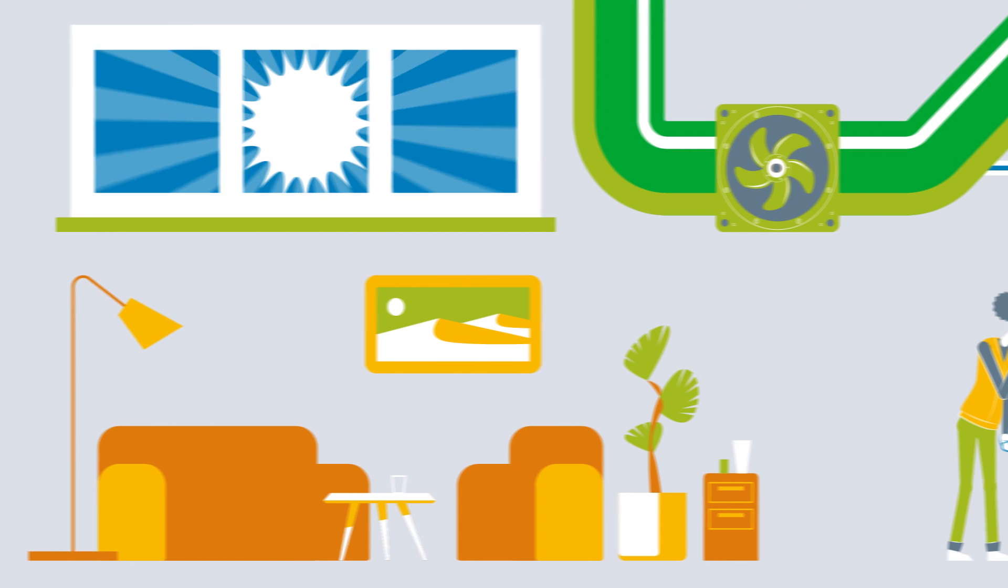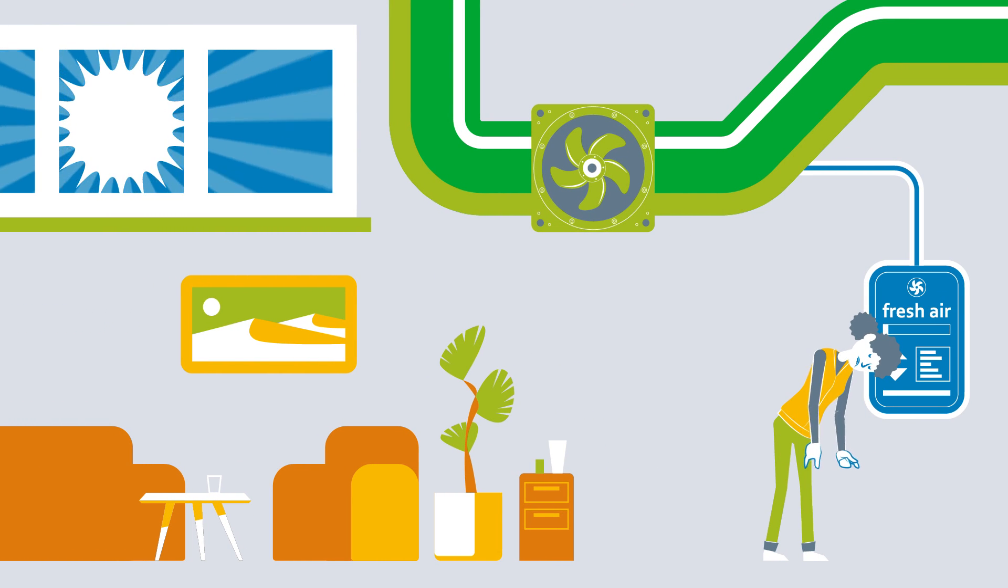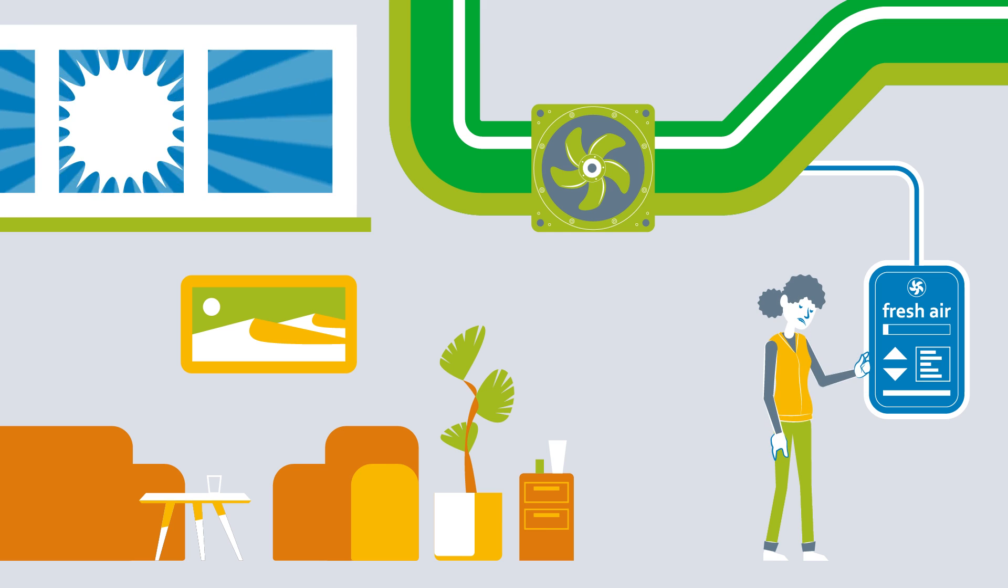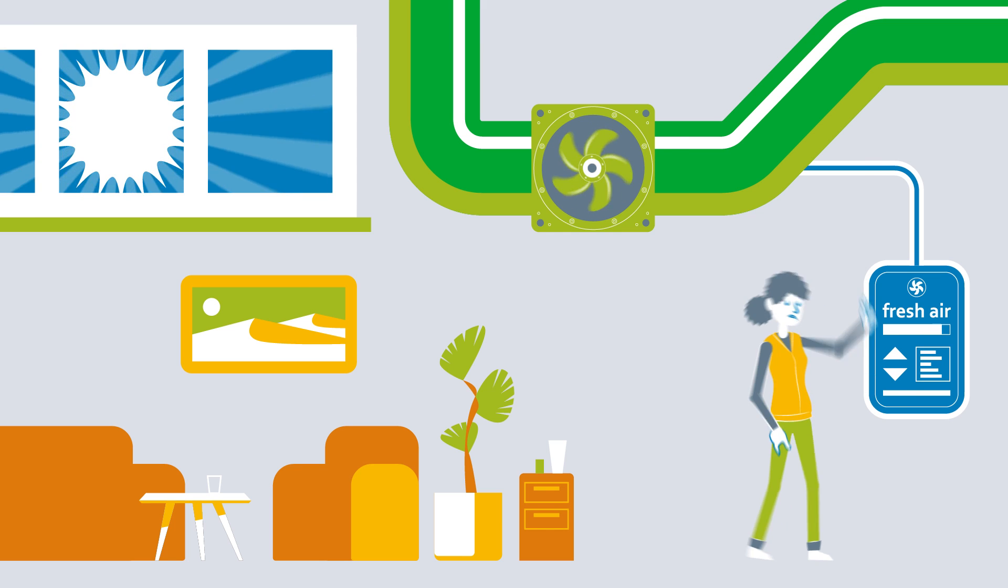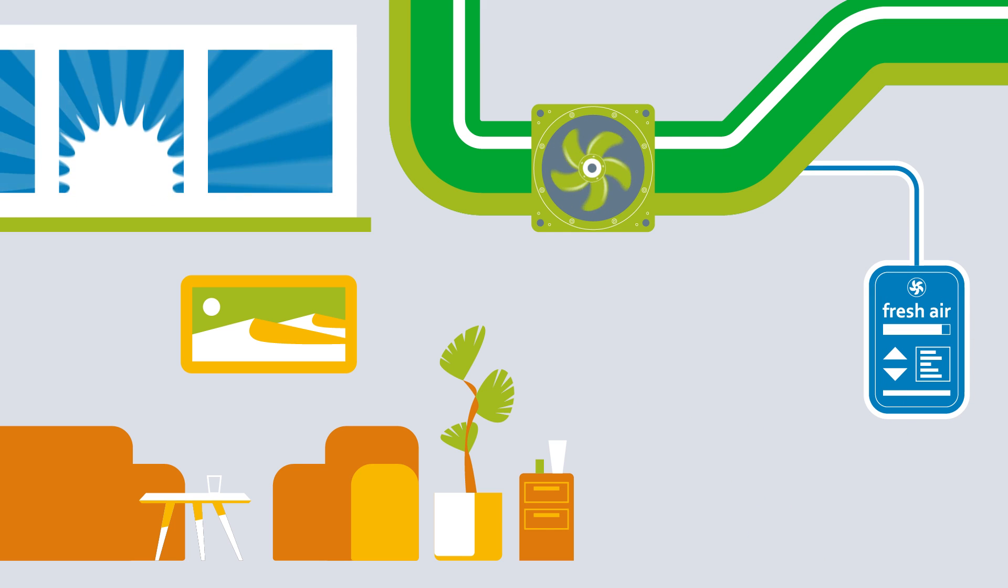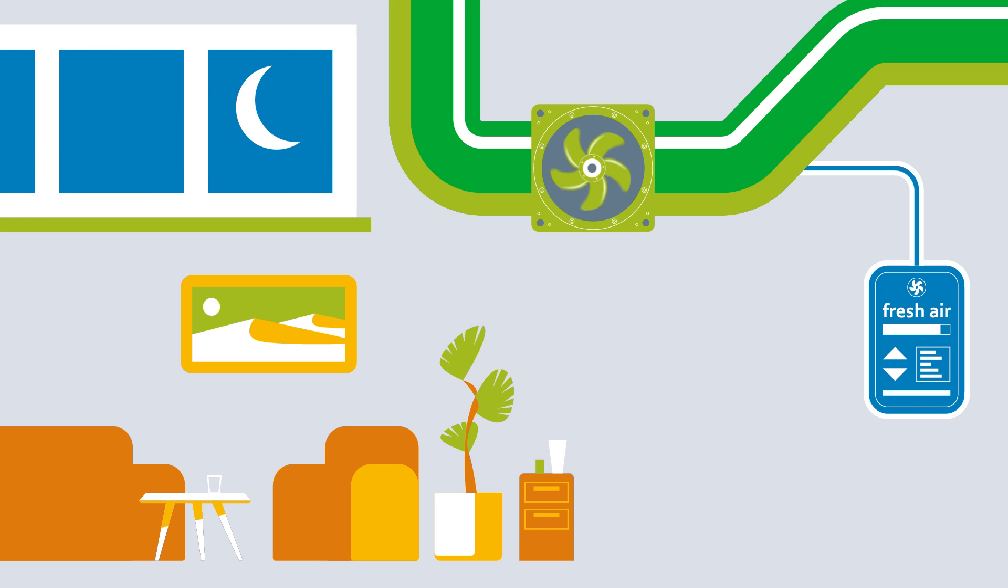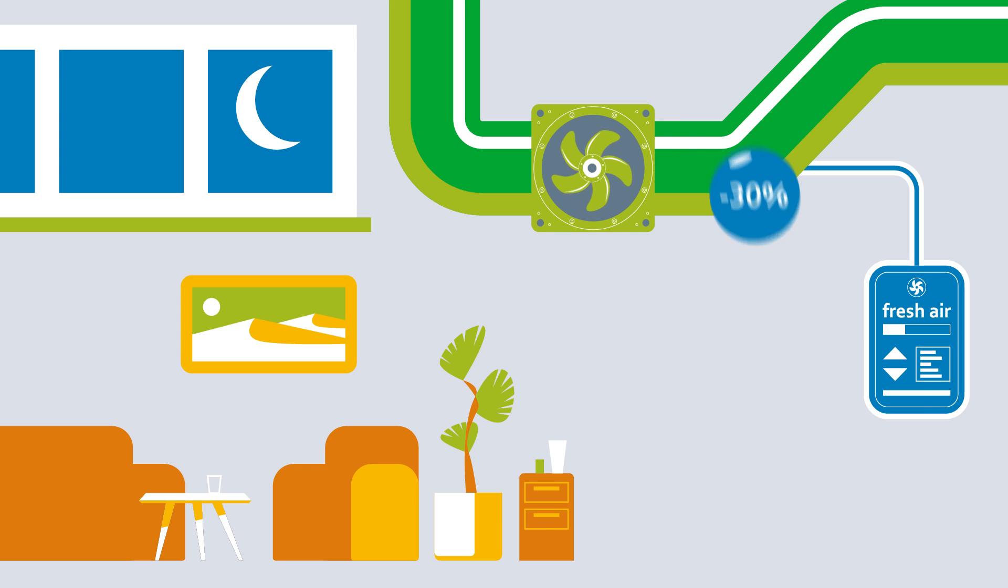A retrofit offers particular potential for savings if the retrofit enables the airflow to be regulated as required. For example, it's possible to adapt day and night rhythms. Over the course of the year, energy savings of 30 to 40 and sometimes over 50 percent are possible.